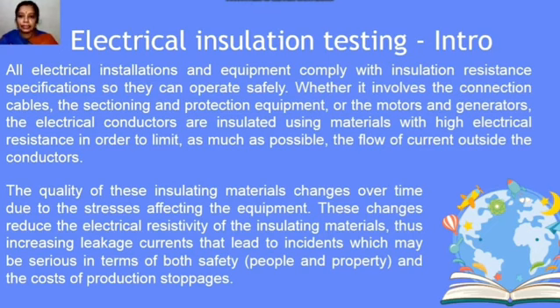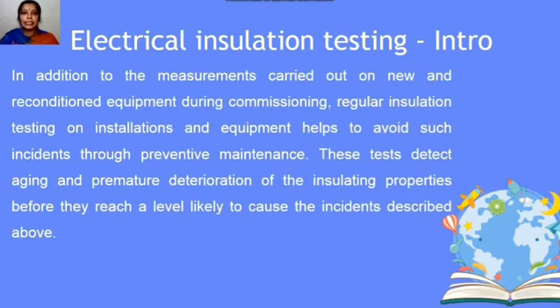The quality of these insulating materials changes over time due to stresses affecting the equipment. The stresses may be electrical stress or temperature stress. These stresses reduce electrical resistivity, thereby increasing the leakage current, which leads to serious safety concerns for operating people, property, and cost of production stoppages. Regular insulation testing helps avoid such incidents through preventive maintenance, detecting aging and premature deterioration before they cause incidents.